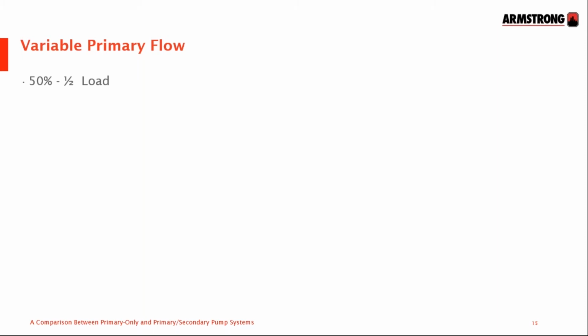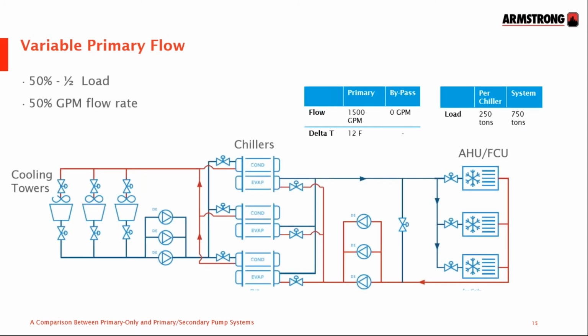Moving down to half load. Now here we're provided with some options. We can continue to run all three pumps or shut one off. We can run all three chillers, or we can shut one down. We could run three pumps and two chillers since the pumps are headered. This is where chiller plant optimization comes in to decide which is more energy efficient.